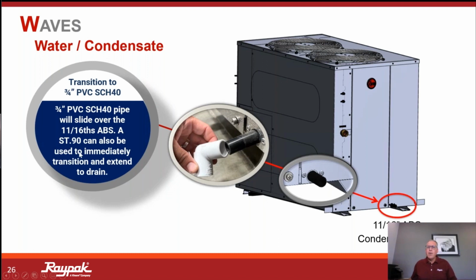And Devin, I don't think Devin is here today. If he's online, I'll double check here. Yeah, I don't see him joining us today, but Devin spent some time trying to come up with a method to get us to transition over to 3/4 inch PVC Schedule 40 so that we can take that to your sanitary sewer. This is going to produce condensate, and we want to be able to transition over to the standard, typical size of 3/4 inch, or even on multiple units if we have to upsize to 1 inch.